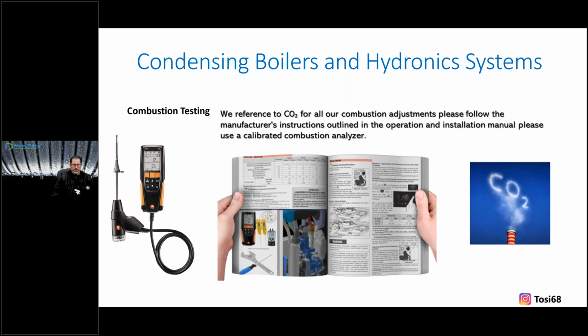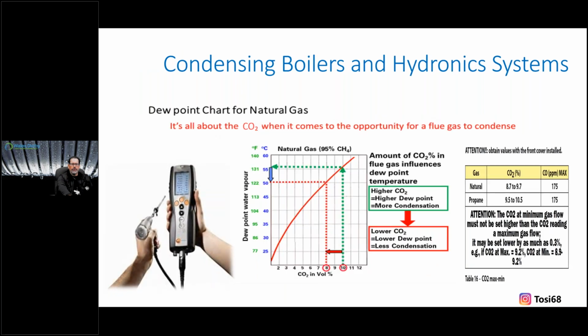To embellish a bit more on the process - talking about lowering water temperature, you have to understand what the combustion analyzer is doing for you. It sets up the CO2, which is where we set the bar for at what temperature we'll see the collapsing of flue products, which becomes condensation. This chart shows you, based on which manufacturer's installation guide, what they're requiring with the combustion analyzer to set up the burner. They might do this at the factory, but they don't have the same quality of gas or air that you have on the job site. They're certifying something before it leaves the factory floor.